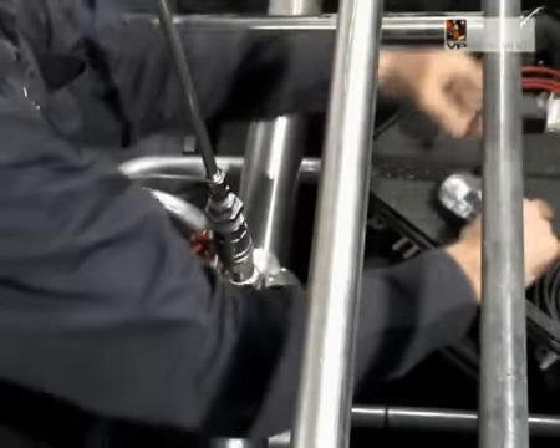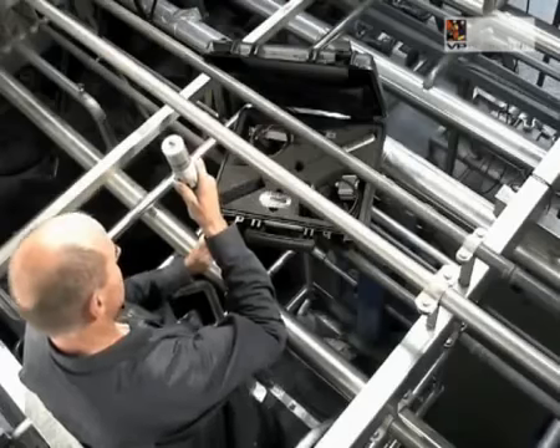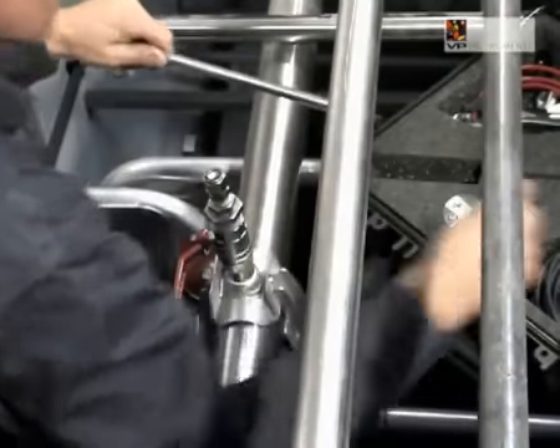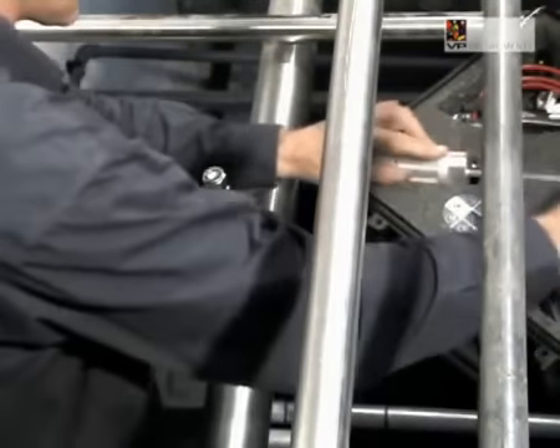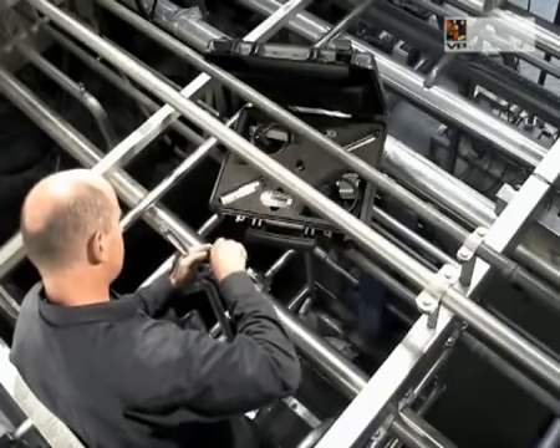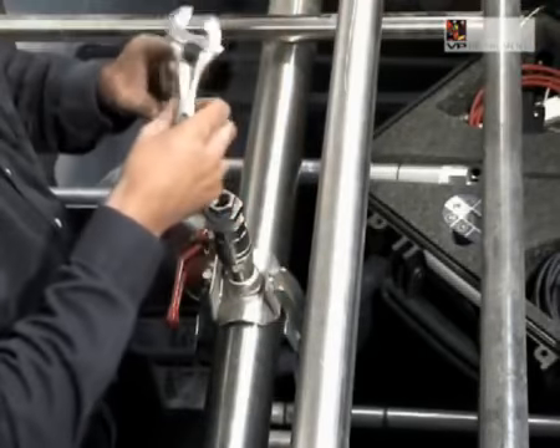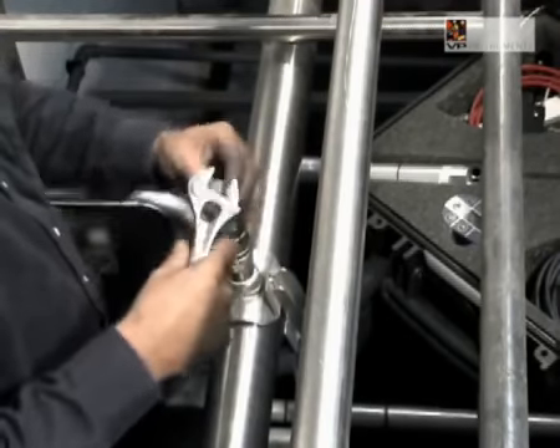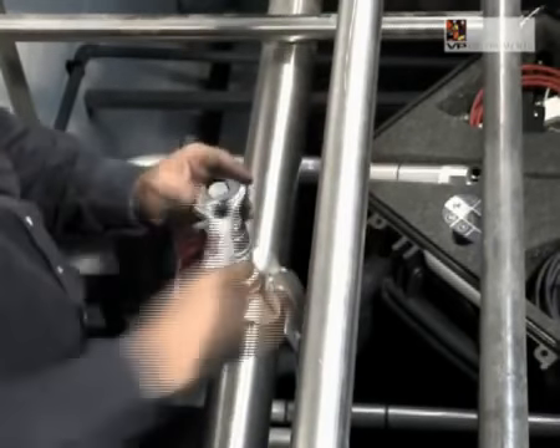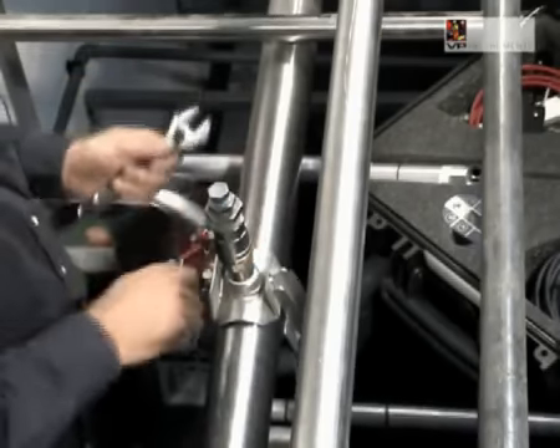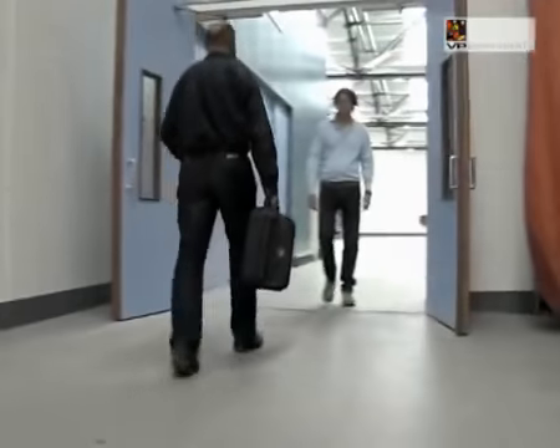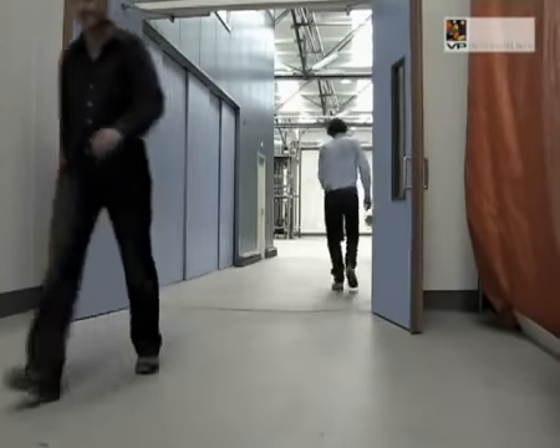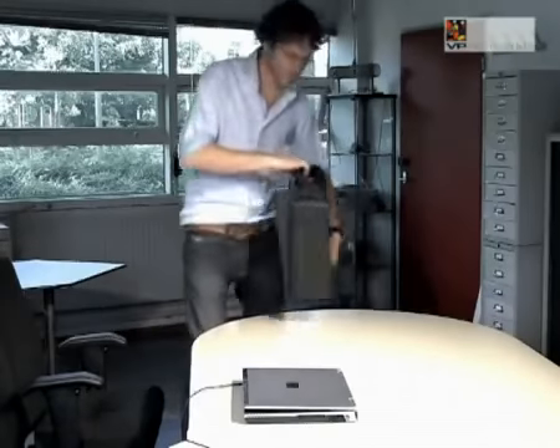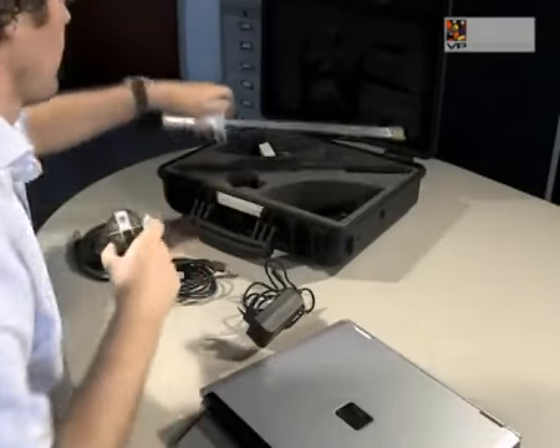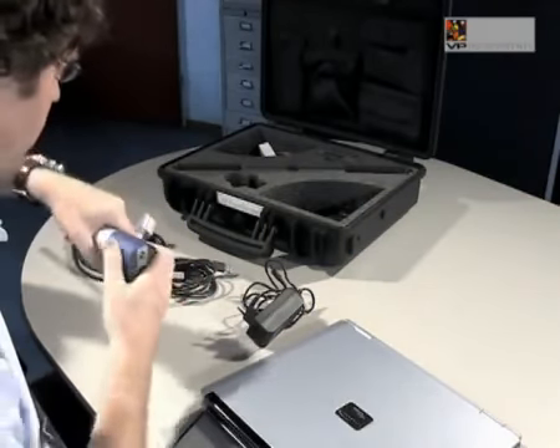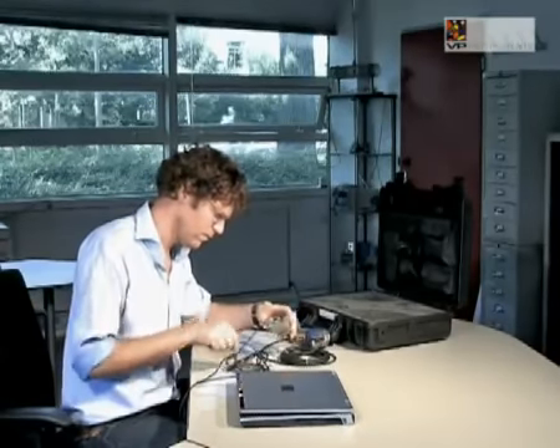Carefully open the compression fitting and gently retract the probe till the safety line tightens. Make sure that the VPFlowScope probe is completely retracted and then close the ball valve. When the ball valve is completely closed, you can take off the safety line. Take the display off and remove the probe. Place the protection cap over the sensor and put everything back in the case. The VPFlowScope can now be taken to the office for data analysis.